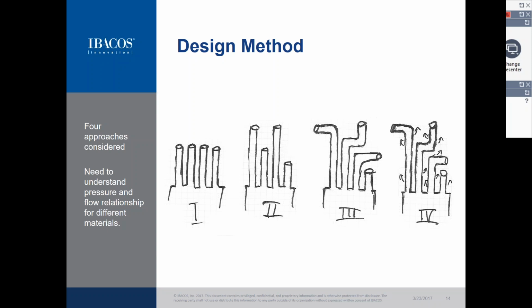We see a little cartoon rendering here of the 4 different design methodologies, basically from the most simple, where we assumed every duct got the same amount of airflow regardless of length, up through a scenario where we're considering the exact length of each run, the number of elbows, heat loss along the length of that duct. And ultimately, we settled on something of a middle road design methodology where the duct length and number of elbows is considered in predicting the airflow through the duct.